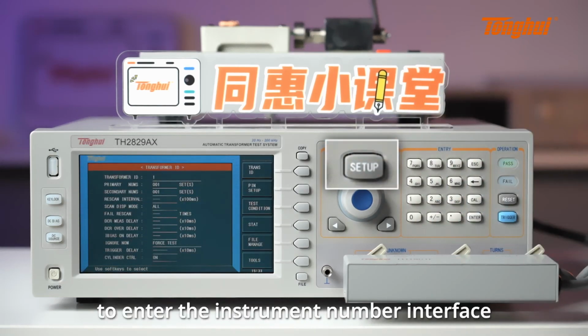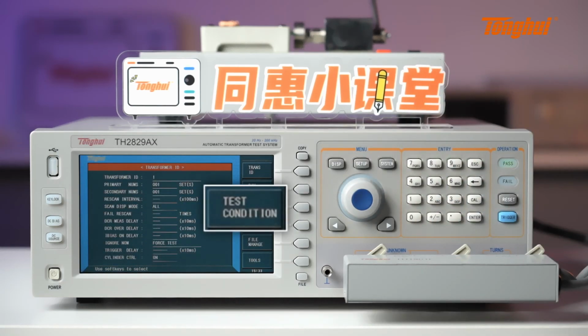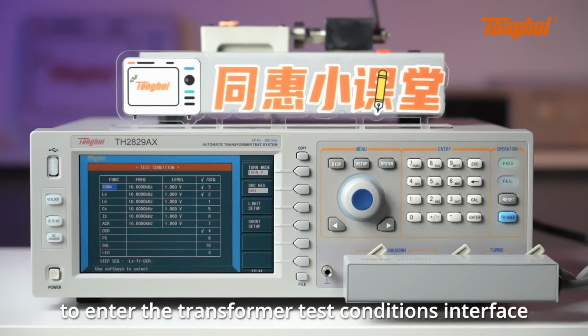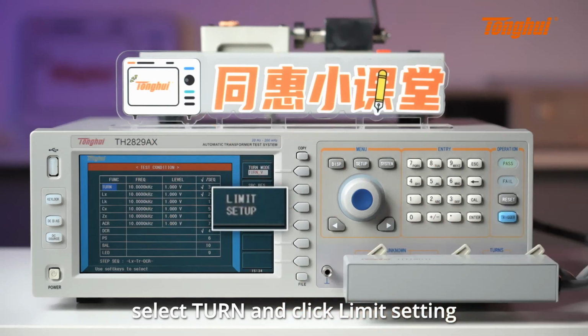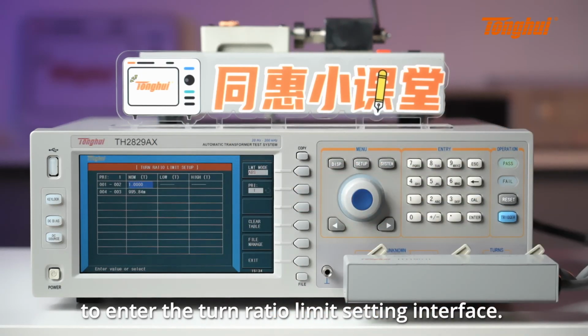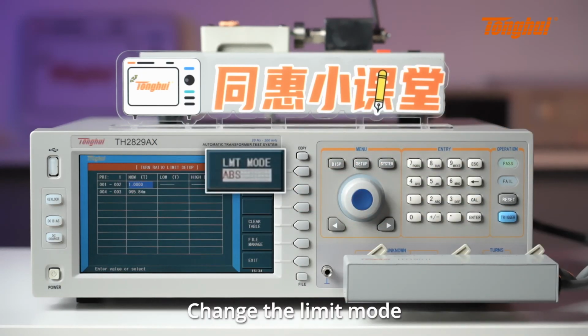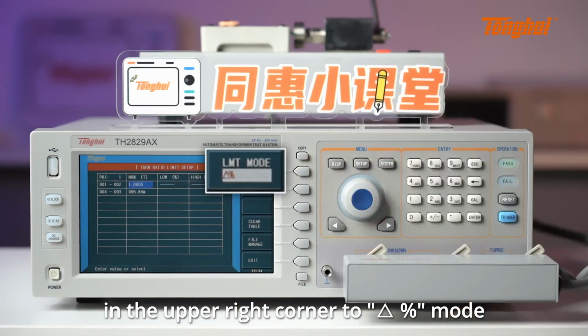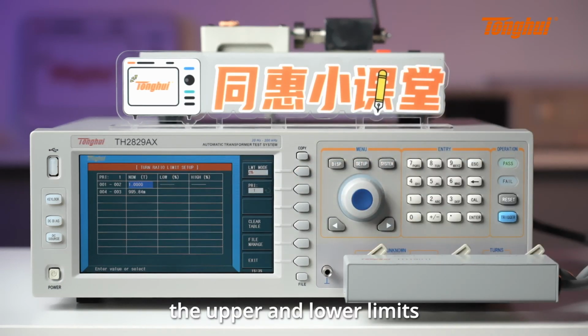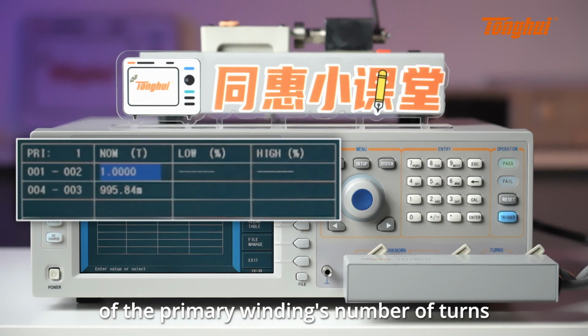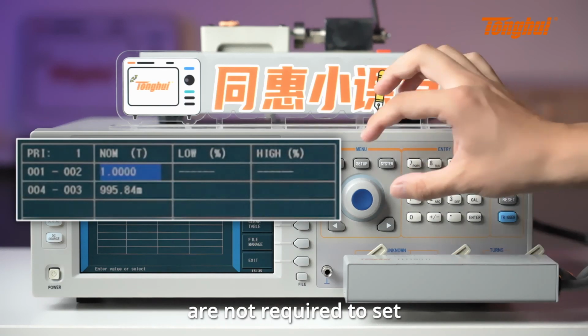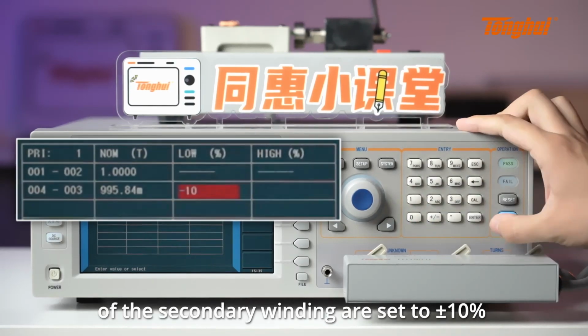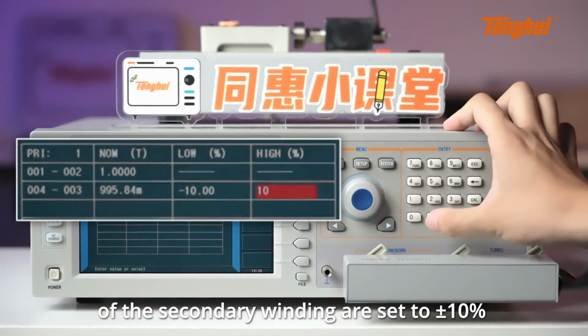Click Setup to enter the instrument number interface, then click Test Conditions to enter the transformer test condition interface. Select Turn and click Limit Setting to enter the turn ratio limit setting interface. Change the limit mode in the upper right corner to percentage mode. The upper and lower limits of the primary winding's number of turns are not required to set, and the upper and lower limits of the secondary windings are set to negative to positive 10%.